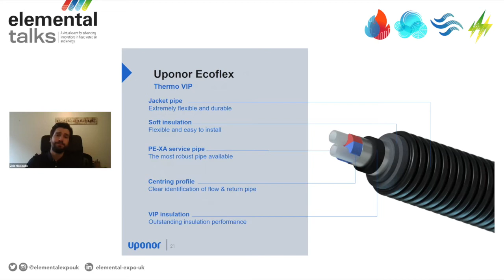Here you can see a very nice illustration of the heat losses of our pre-insulated pipe buried in the ground with and without the VIP insulation. So you can see the effect of the VIP insulation layer towards reducing the amount of heat that is transferred from the water inside the pipe to the PEX foam insulation and then through the jacket to the ground. And then you can also see the reduction of the temperature spread within the ground after the heat goes out of the jacket. You can understand that overall it contributes to achieving approximately 60% lower heat losses for the same jacket sizes.